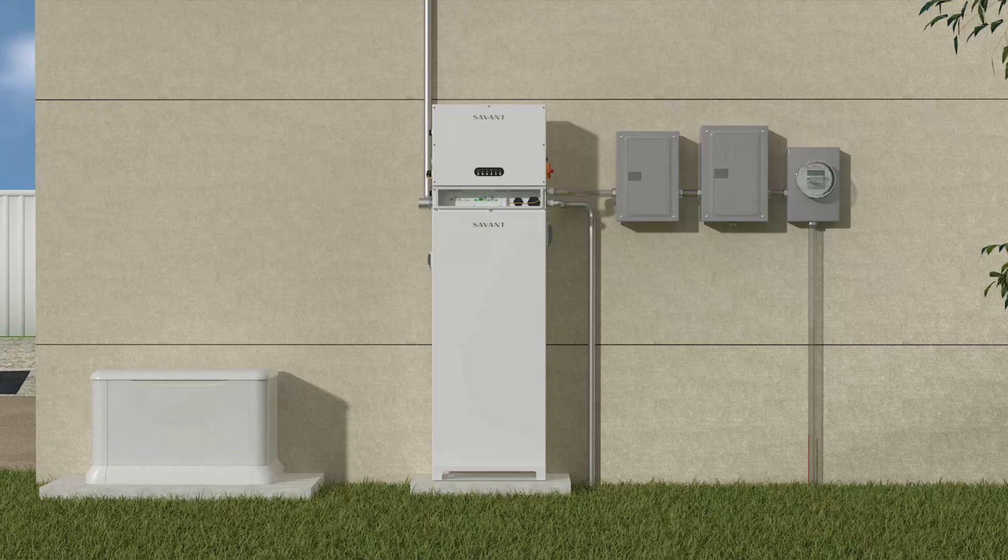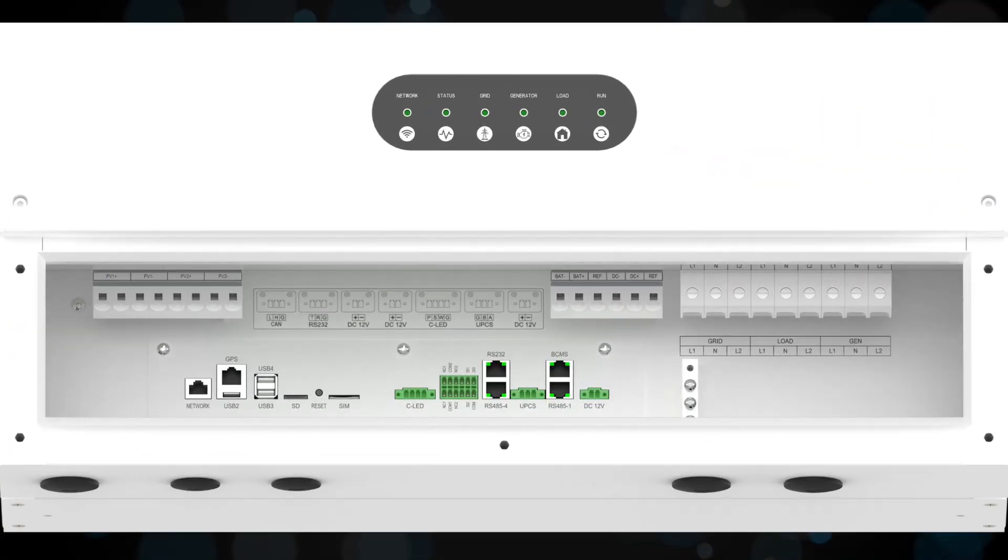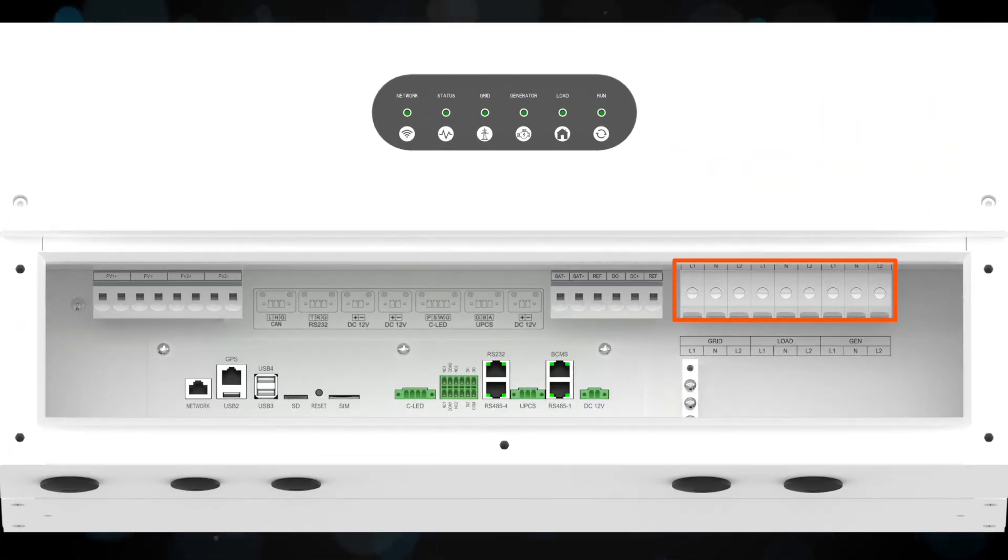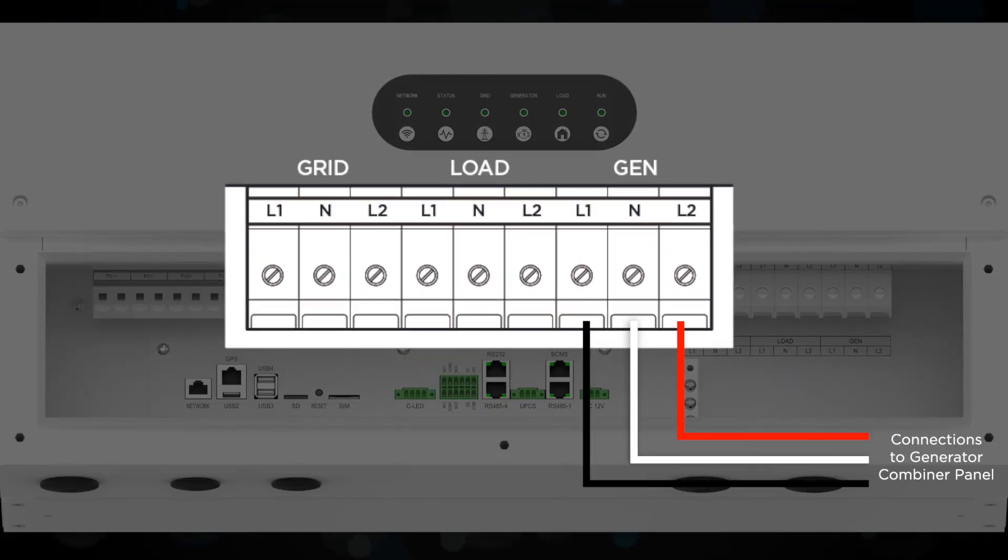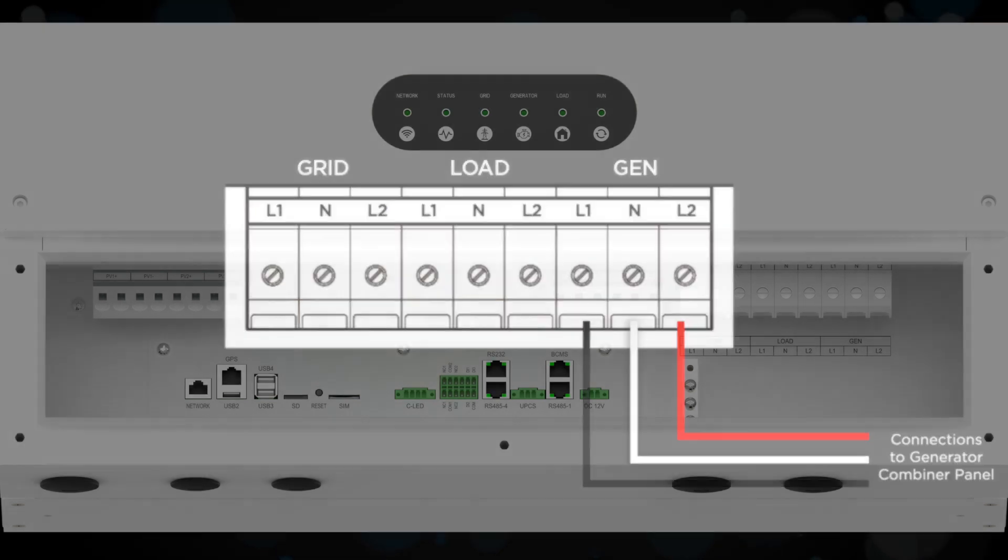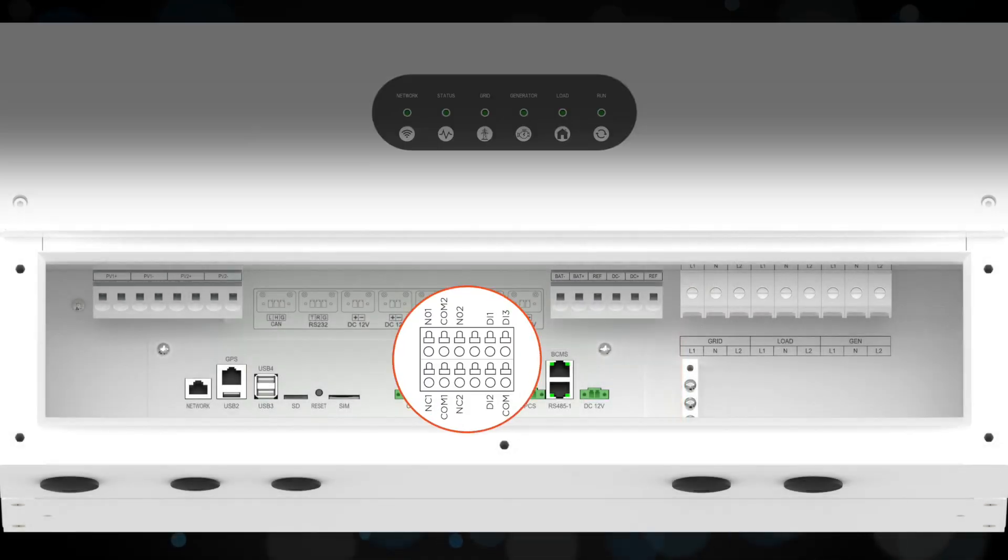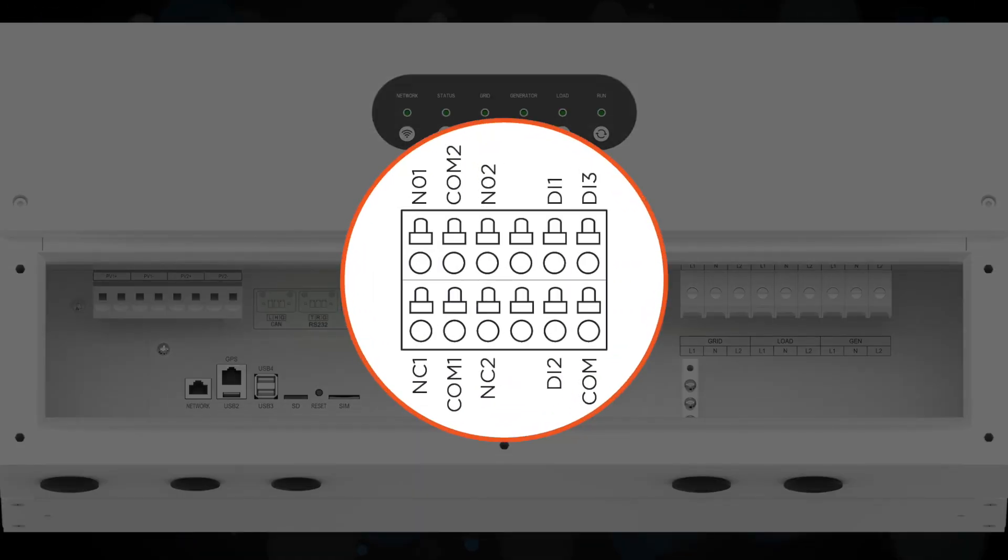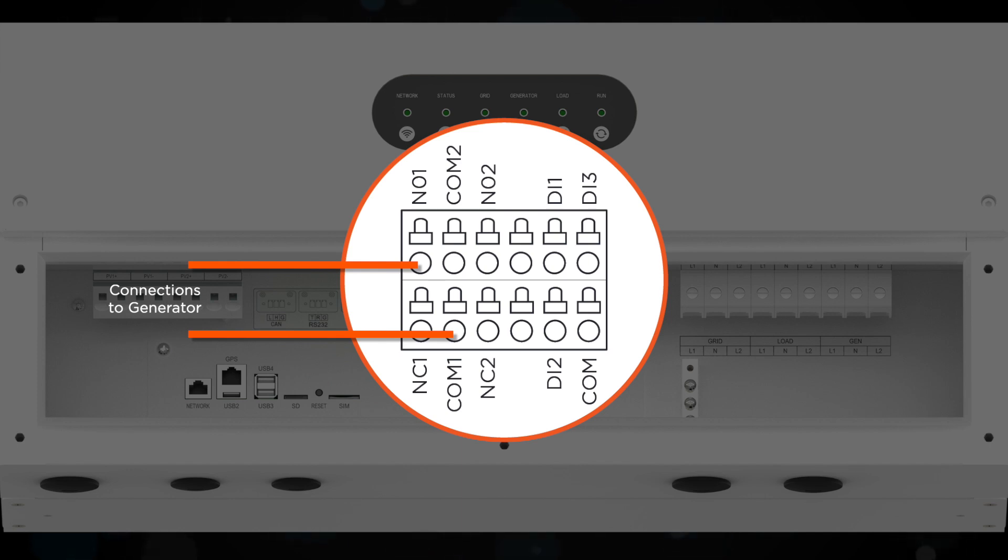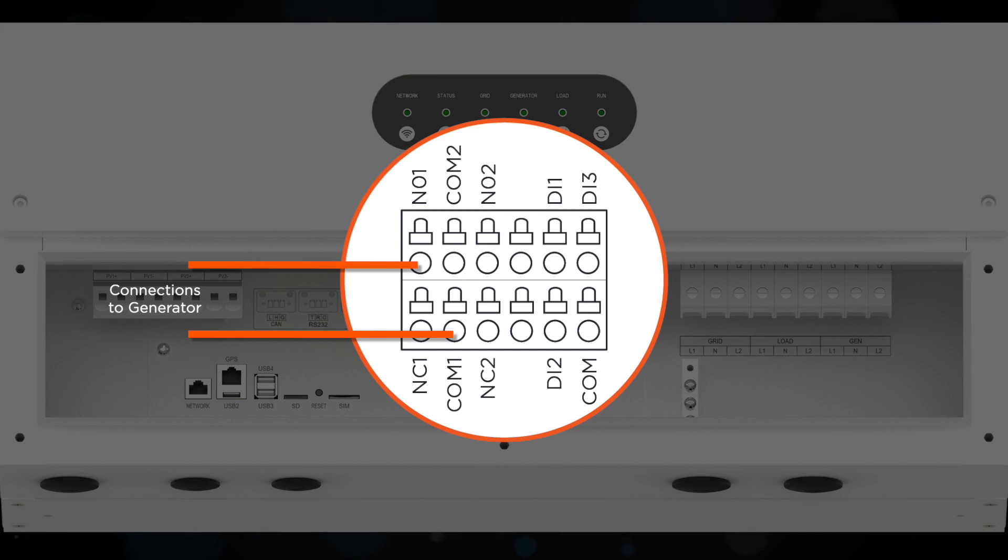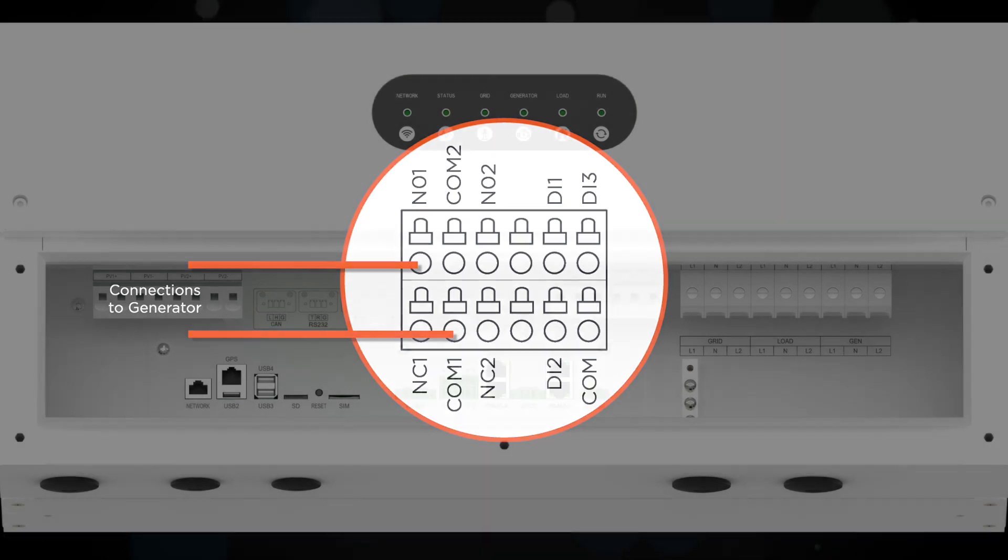Now, let's look at the physical connections on the inverter. On the right, we see the connection for the generator input. We'll wire from here to the combiner panel. In the middle are our low voltage connections. Connect the two wire generator start leads to the NO1 and COM1 ports. This connection needs to be made at each inverter in the system and wired back to the generator to trigger it to start when needed.